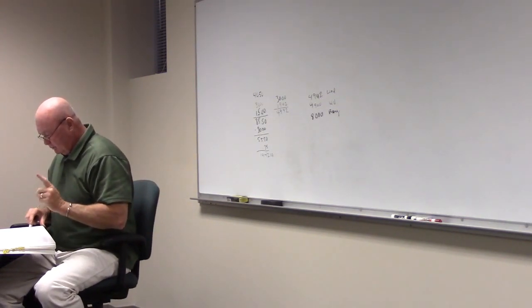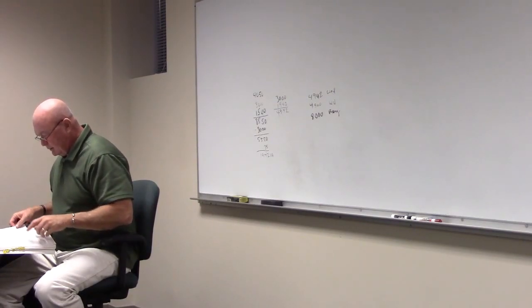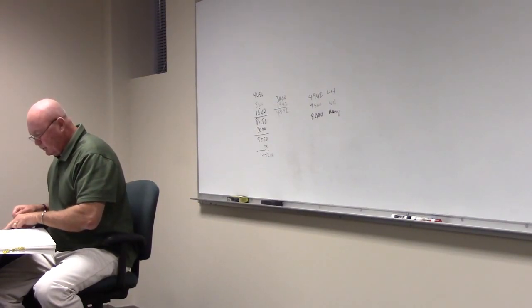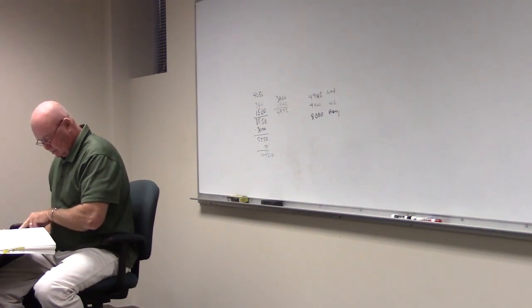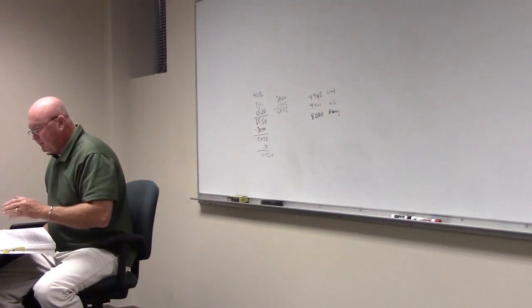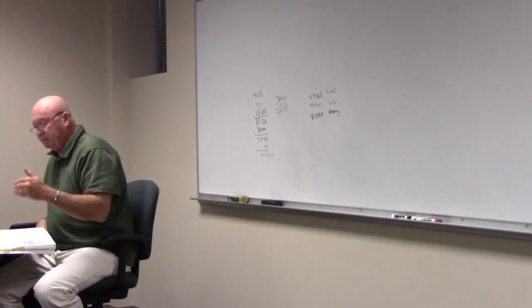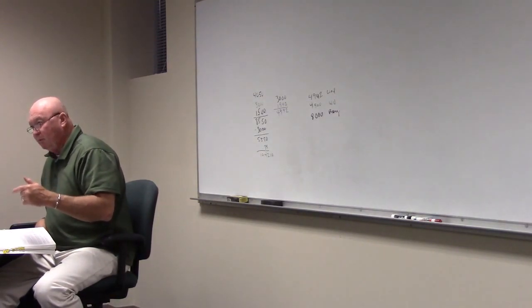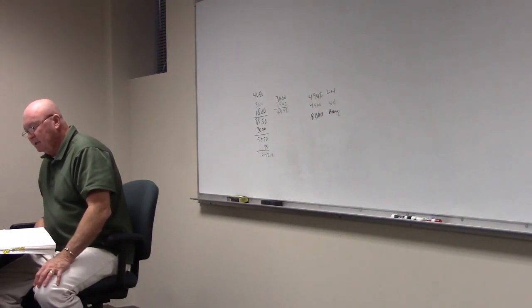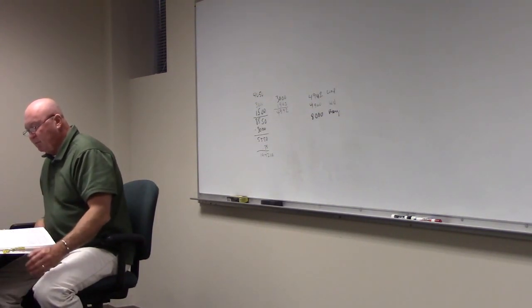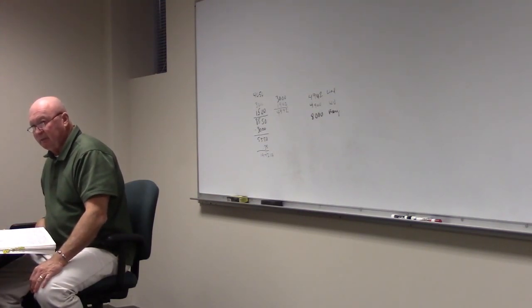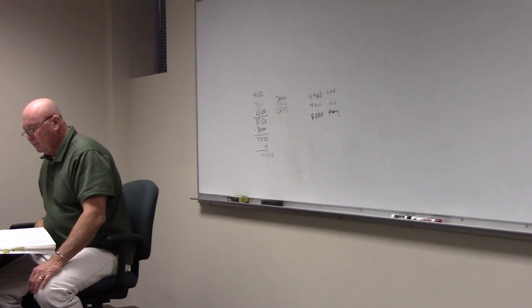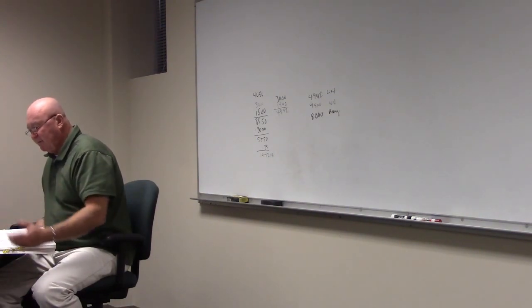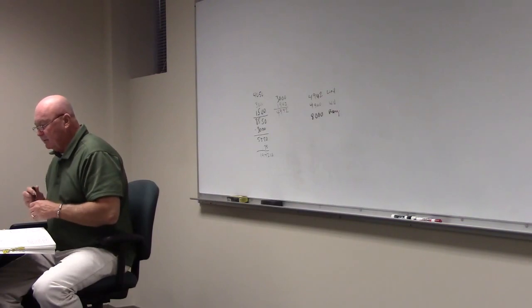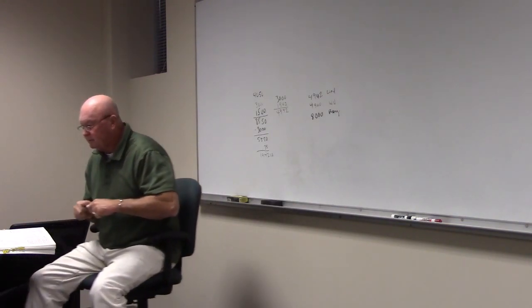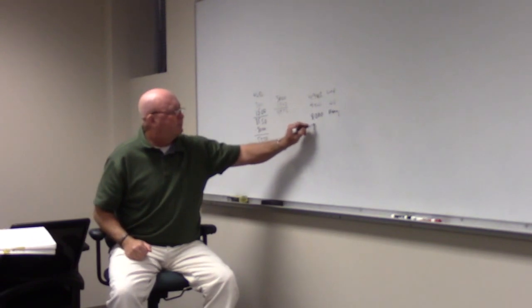Clothes dryer, while we're there, let's turn to 220.54. Clothes dryer. First of all, the minimum that you can have for a clothes dryer by 220.54 is how many watts? 5,000. But our clothes dryer is 5.5 kW, which is how many watts? 5,500. And so how much is our value for our clothes dryer going to be? 5,500.